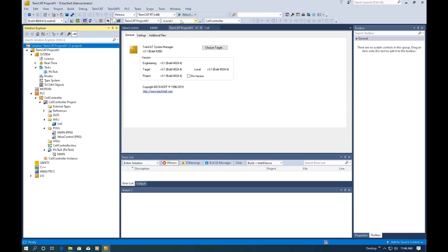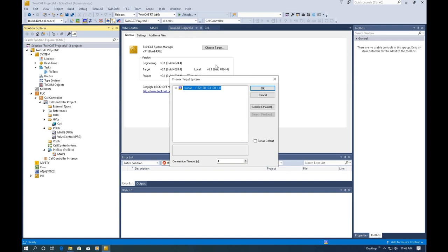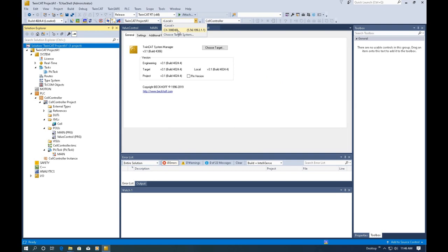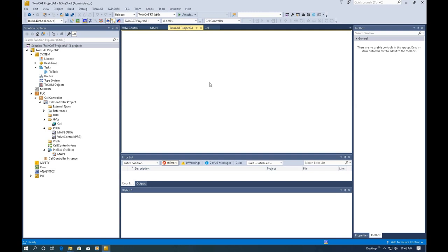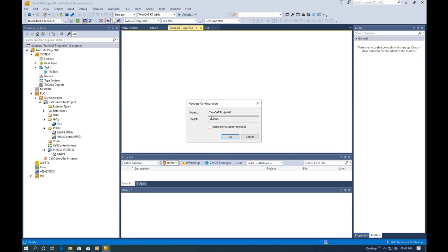Because we are trying to use the local system, you need to switch the target to 'Local'. If you've connected to controllers before, you can select a previously connected controller; otherwise select the actual controller to enable the external communication channel. To test the simulation, select 'Local' here, then click 'Activate Configuration' to download the configuration to the local simulation system. The target is Local and the project is our current project — select OK.